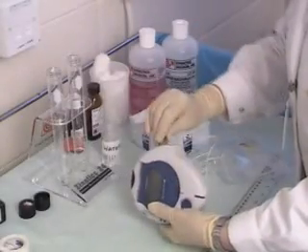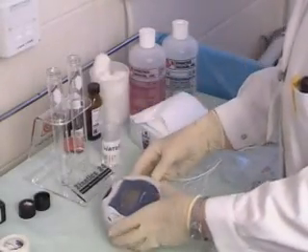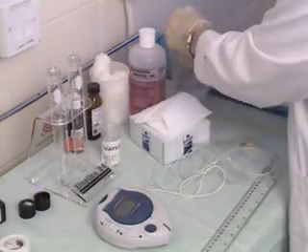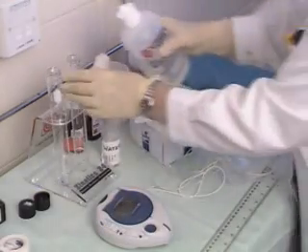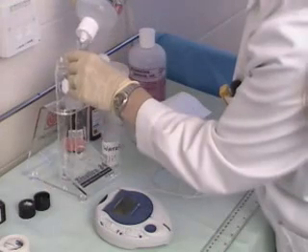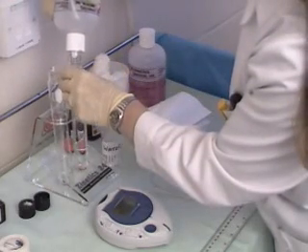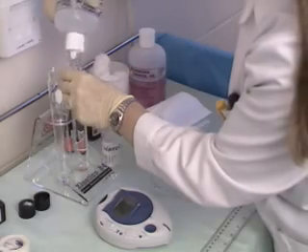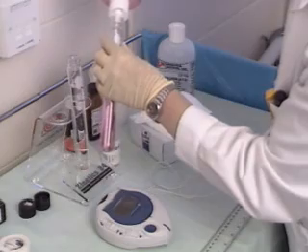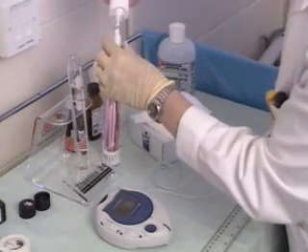The recorder must be calibrated before each new patient study. Calibration ensures that the system, both the recorder and the catheter, is accurately detecting the pH value of the environment. 2 buffer solutions of pH 7 and pH 1 are used, as these represent values at either end of the pH range normally encountered within the esophagus.